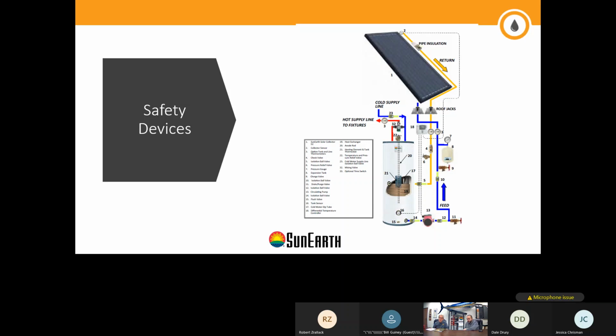This drawing again is residential. Most residential systems do require a mixing valve. Commercial is a little different; that can vary based on design. But you don't want to scald anybody. Your solar tank could be 140, 150, and you don't want that going directly to a fixture. For sure not. And then, as Bob said, that changes completely when you go from residential to commercial or industrial application, when you're looking for low-grade steam and stuff like that. You still have safety devices introduced into the system design, but it just works a little bit differently.